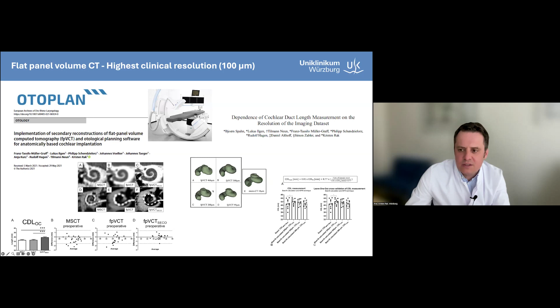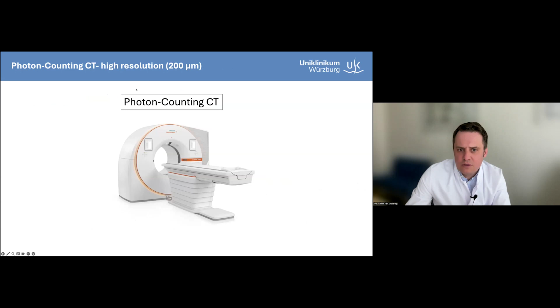Also in the last years, the photon counting CT came into the field of imaging. And I would like to shortly just talk about this. Photon counting CT has also quite good resolution, about 200 micrometers. And what's the advantage of photon counting CT? It's a special detector. Normally you have a typical pixel size in an energy integrating detector of about 500 by 500 micrometers. And the photon counting CT, it's much smaller with 150 times 176 micrometers.